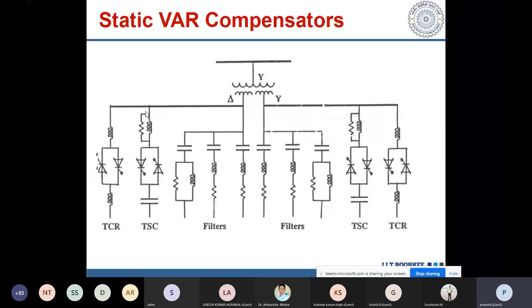Now, we have seen what are the different harmonics present and what are the various causes of harmonics in the current waveform. Now, when this particular distorted current is drawn from the supply, the voltage drop across this particular impedance will be different for different harmonics, because the impedance due to the inductance will be proportional to frequency. The more the frequency, the more will be the drop, and therefore the drop across this particular impedance will be different for different harmonic currents.